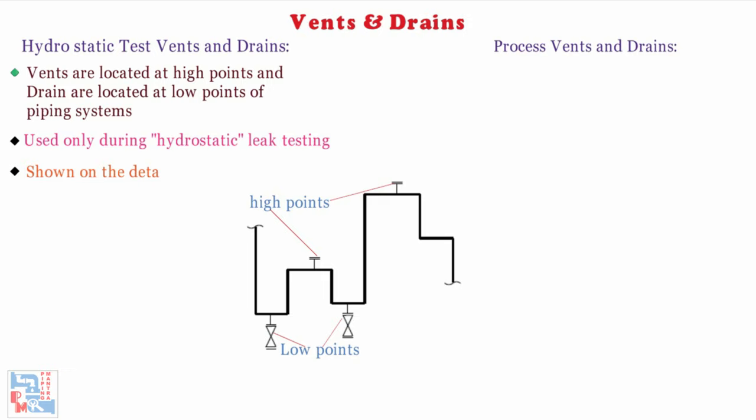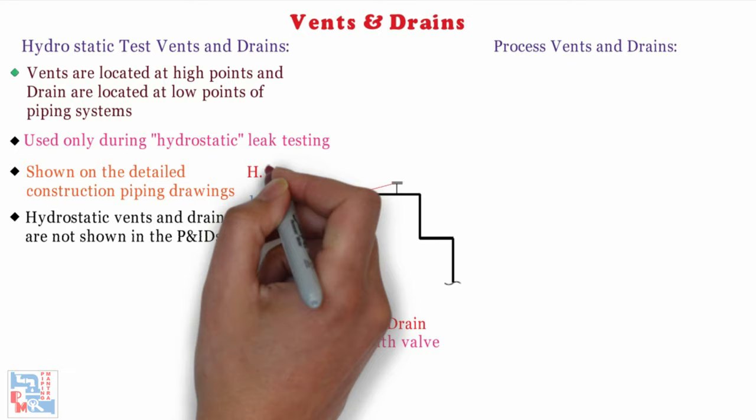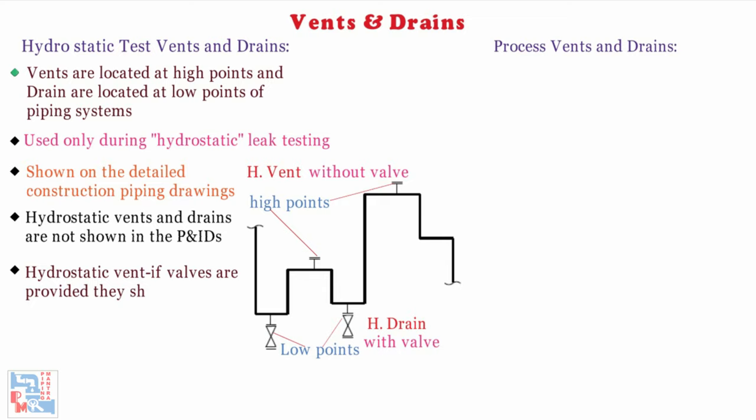Generally, hydrostatic vents and drains are not shown in the P&ID. Hydrostatic drains are provided with valves and hydrostatic vents are normally without valves. However, if valves are provided, they shall be shown in the P&IDs. Hydrostatic vents and drains which are to be marked on P&IDs should be tagged as HV and HD respectively to differentiate from the process vents and drains if required to be shown.